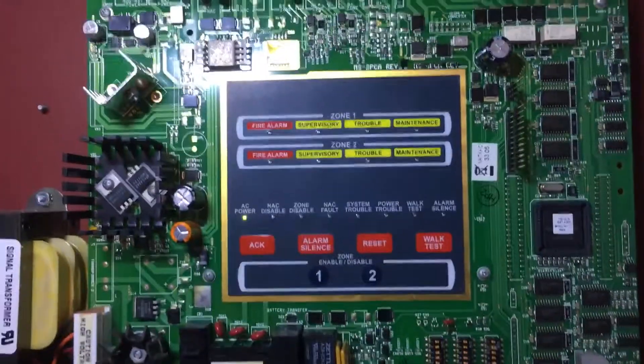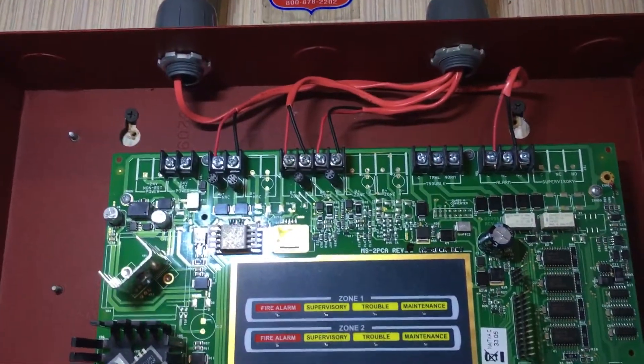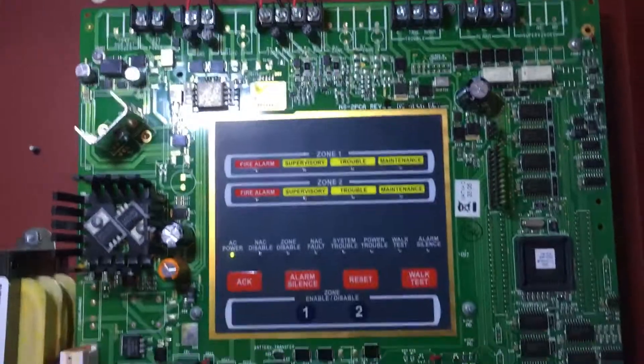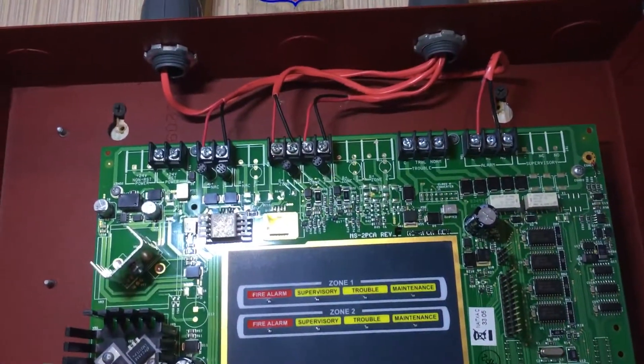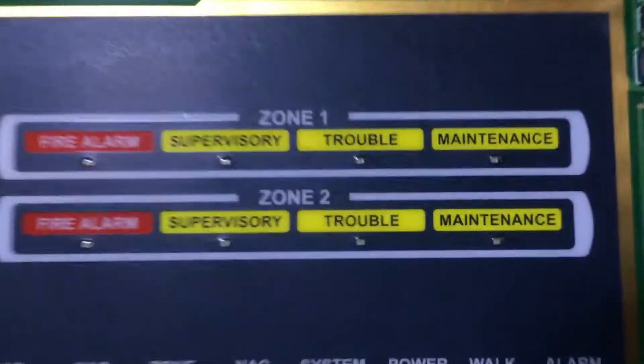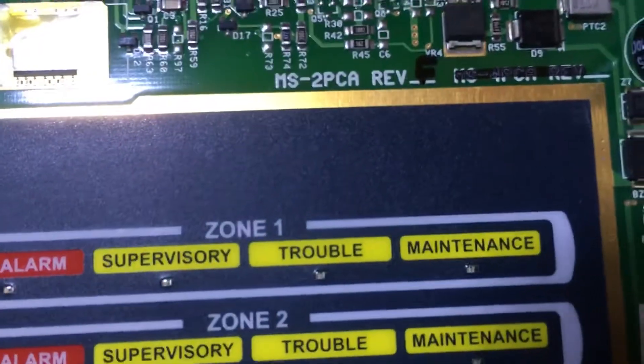As you can see, the system is normal. That is because the panel can see each end-of-line resistor on the system. So, if I were to disconnect the zone 1 terminals, or the wires, it would go into a zone 1 trouble — it would say system trouble, zone 1.